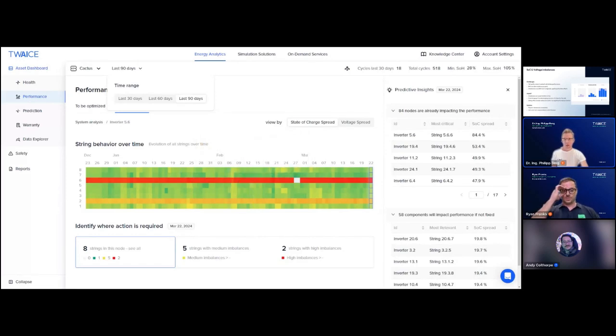Let's look into some negative effects, which I already covered a bit. Here you see the daily cycles for this node, and you see that this string 5.6.6 can contribute much less compared to the other strings. But the actual bad part is if you compare to other nodes which get the same power demand request, all strings in this node can contribute less. So this one string actually limits the whole unit and therefore limits your overall output.